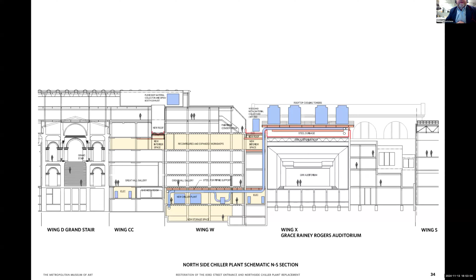That central chiller plant serves 60% of the building—1.25 million square feet of the Met—pumping chilled water to all the HVAC systems in this part of the building. At the Met, the HVAC system and environment are critical for art conservation, maintaining 70 degrees and 50% humidity year round.